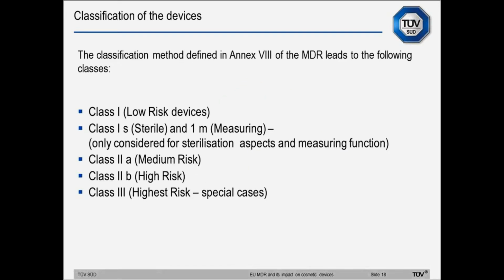So we saw that the classification is the first action of the manufacturer based on his products. This is crucial for choosing the appropriate and convenient conformity assessment. Based on the result of the Annex 8 evaluation of rules, we arrive at 5 classes. Class 1, the low-risk devices, in which the intervention of the notified body is not required, or Class 1 with sterile condition or measuring function, which will be considered just for the sterilization aspects and the measuring functions. Class 2A, medium risk; Class 2B, high risk; and Class 3, the highest risk, considering special cases.